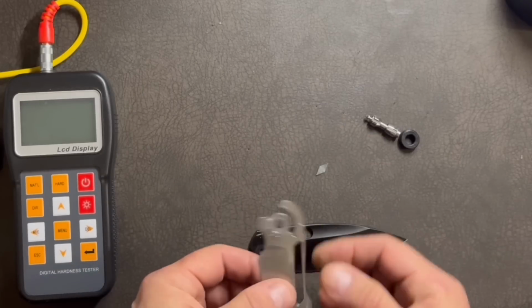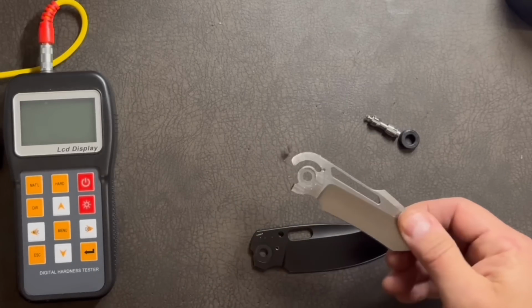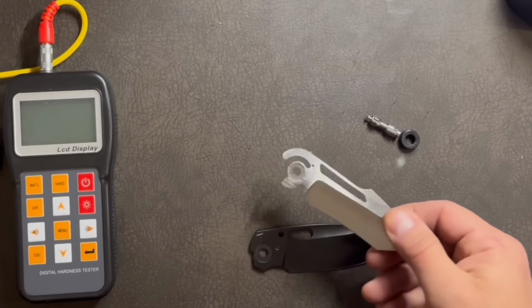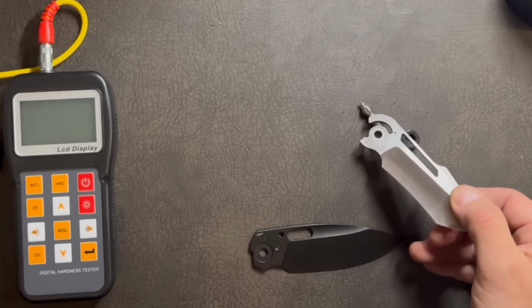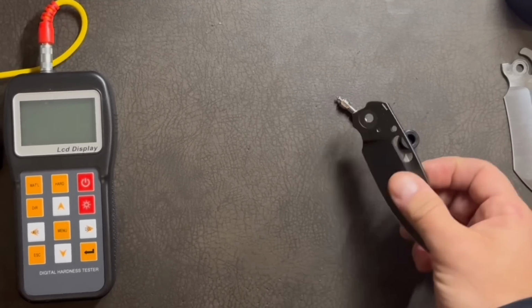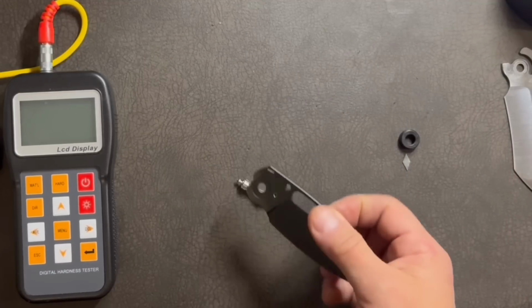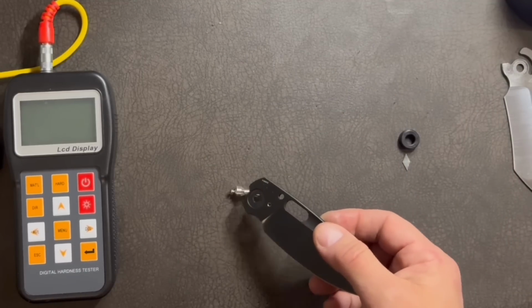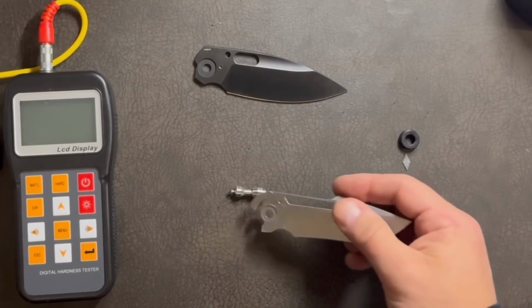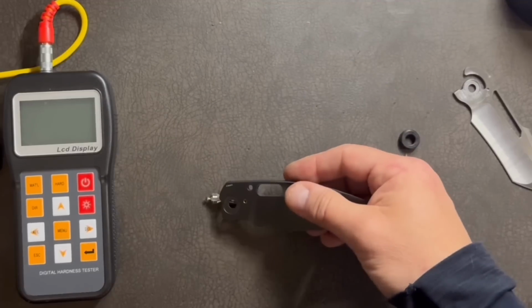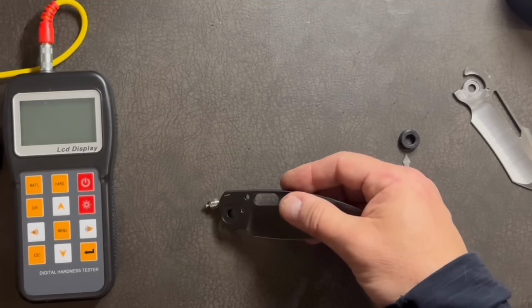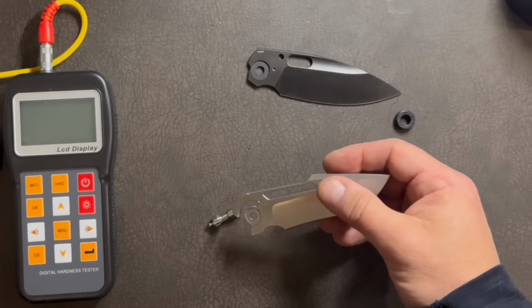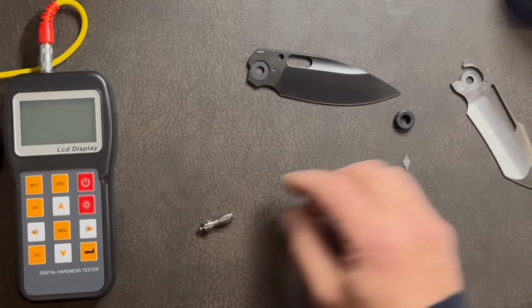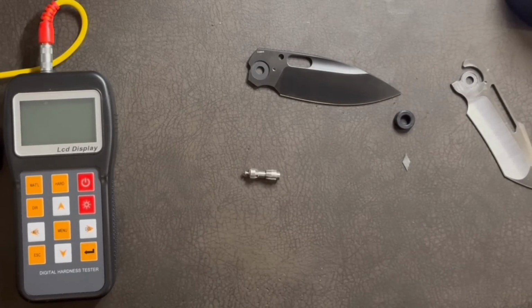So let me try to illustrate here how it looks, not with a random piece of metal, but with the actual probe here. Remember, the probe does have its own magnet inside, and Neeve's blade almost picks it up into the air, whereas the Kunwu blade just barely moves it. So my working theory is that the magnetic field of the blade on Bestech interferes with the magnetic field of the probe and slows it down just a hair. And to the computer, slower means softer material.